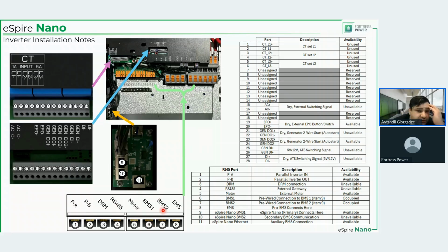BMS1 and BMS2, the ports are obviously here. But the thing is that BMS1 and BMS2 are already connected to the communication board right here. And when you are connecting battery to inverter communication, you will not disconnect anything from here and connect the BMS communication directly to the BMS board. Rather, you will use one of the available or enabled Ethernet ports. That will be eSpire Nano BMS1. That's where you would connect the primary battery to the primary inverter.